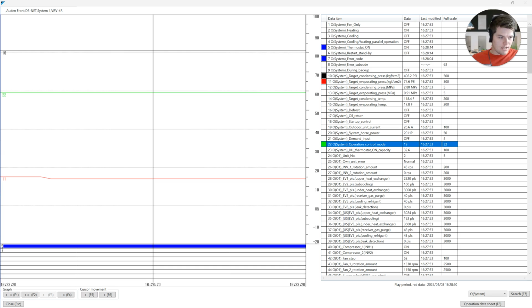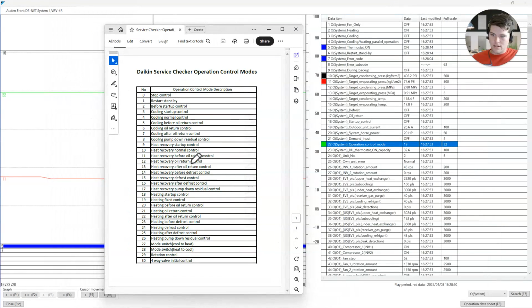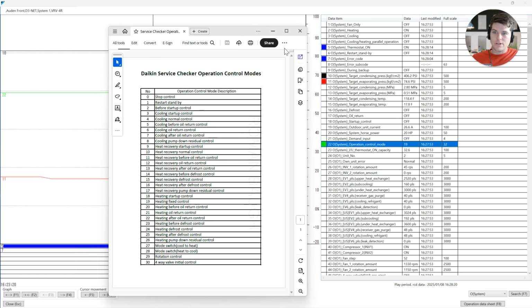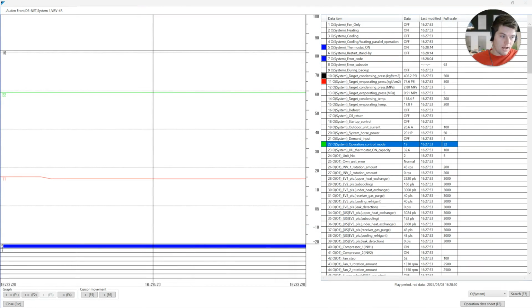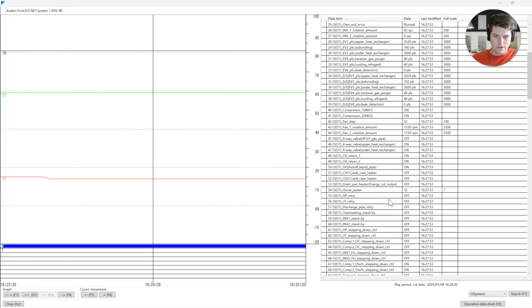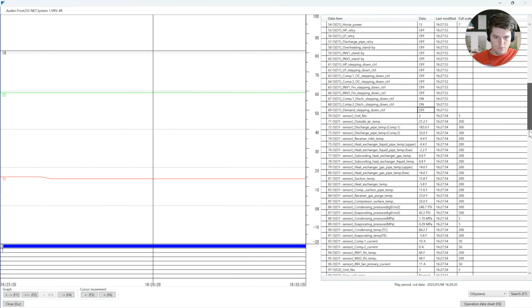19, we know that 19 is what? Let's bring it over. Come on down. 19 is right here, fixed heating control. Fixed heating control means that the system is in fixed heating mode. It has a target. It is going for it. Here we go. So I'm in heating mode, not parallel operation, 100% heating mode. I also have two modules. How do I know that? I can scroll down in my service checker data and I can see that I have two modules.